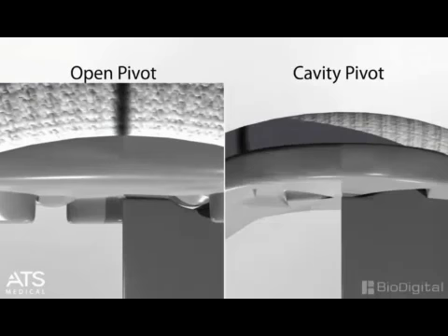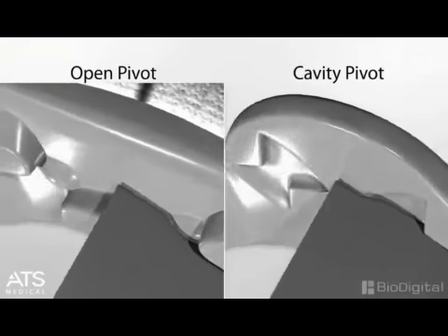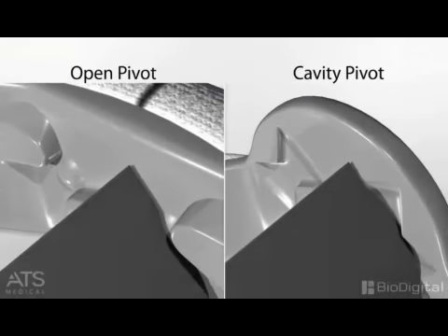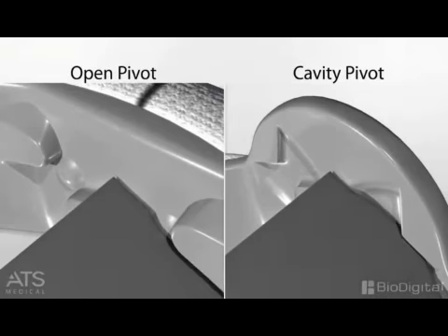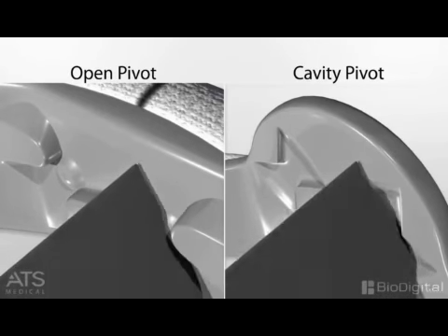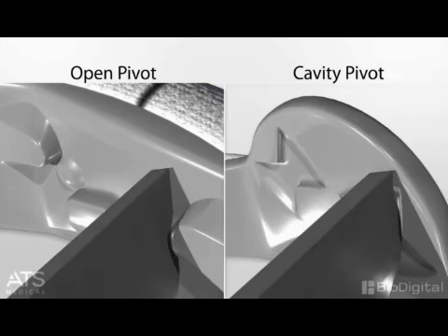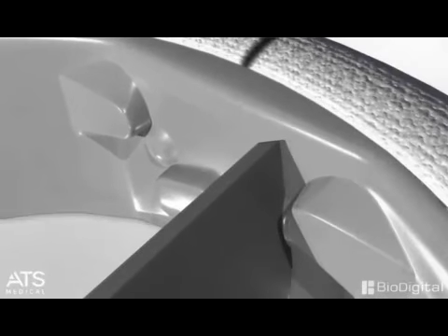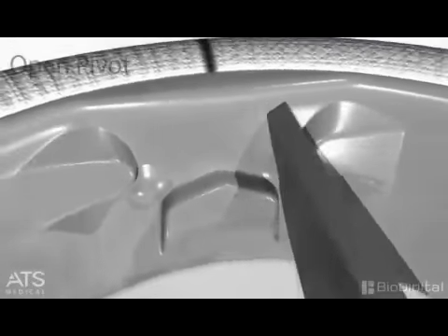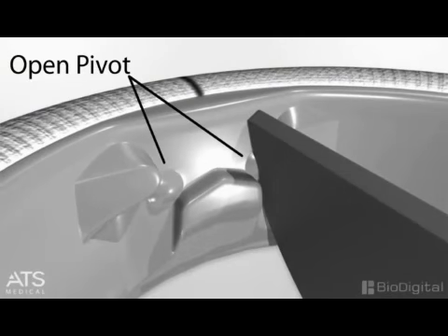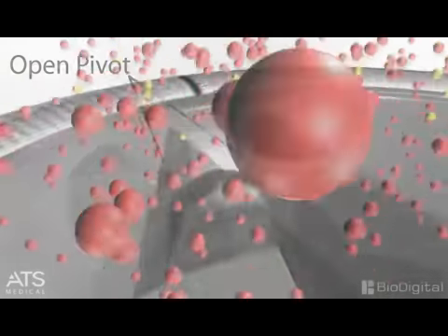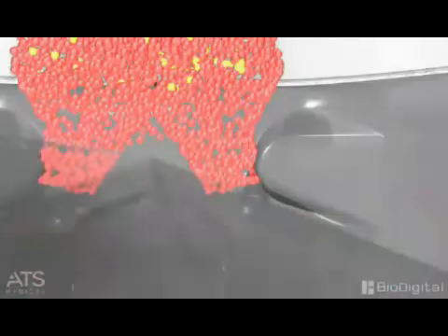The open pivot has positive relief pivot points, rather than the indentations of the typical cavity pivot design, eliminating the pivot recesses as a potential area of stasis and source of thromboembolism. The open pivot heart valve leaflets float on spherical protrusions and are retained in place by leaflet stops. The open pivot is designed to be more open to the blood flow, resulting in a gentler, passive pivot washing in both forward and retrograde flow.